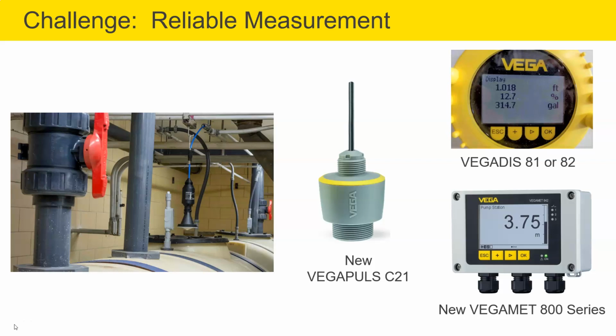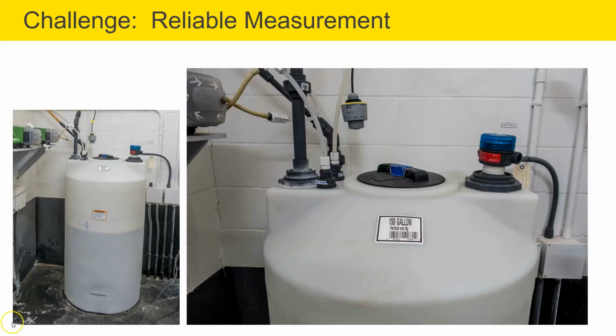This can have an even greater cost impact if the site is a long way from the chemical supplier. Here is another example where the ultrasonic blanking distance only allowed the customer to use about 60% of a day tank. Now they can use 100% of the tank and get an accurate and reliable measurement.